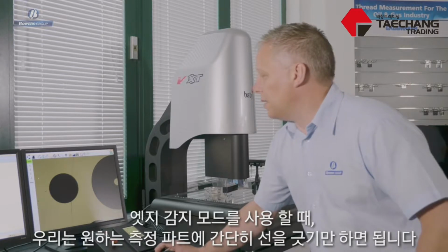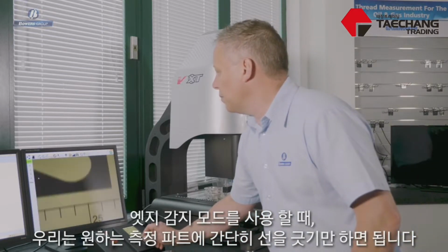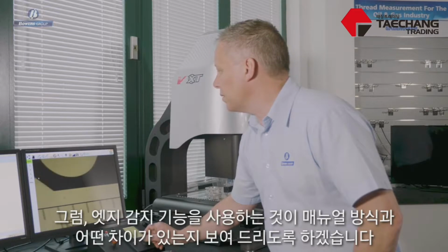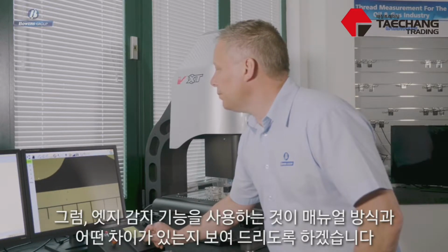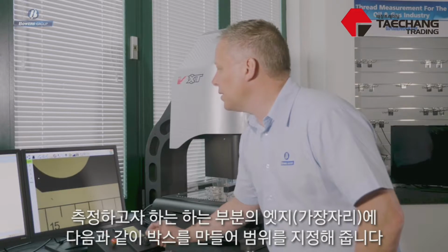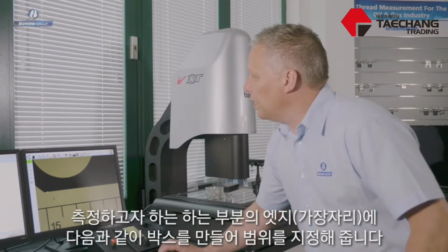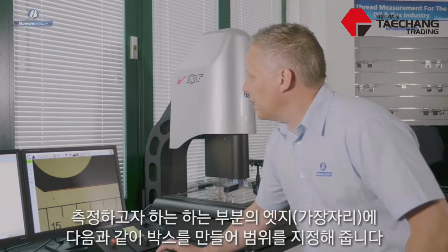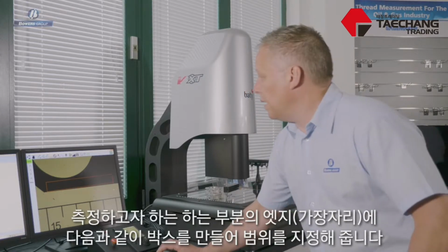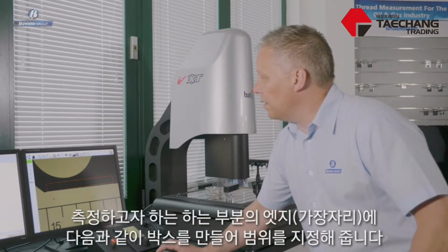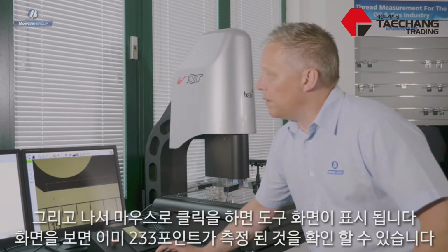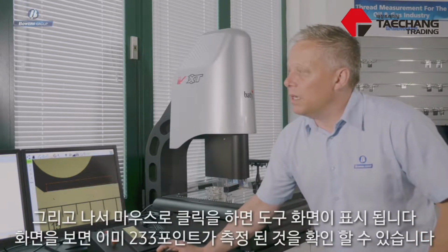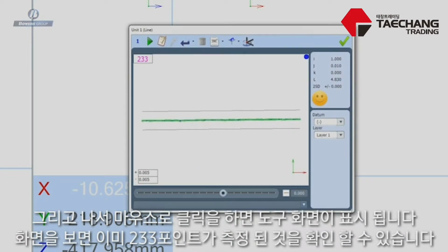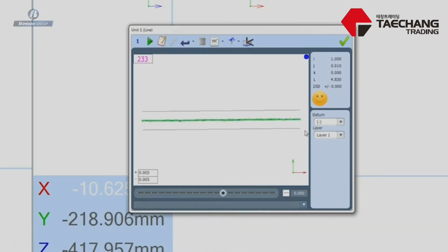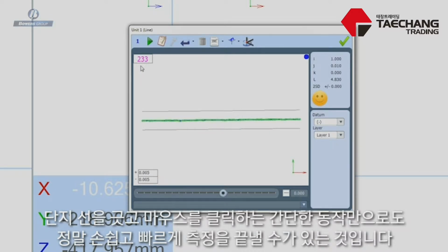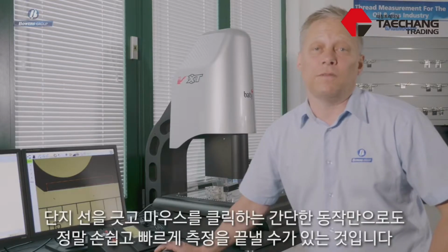So when we take edge detection measurements, I'm just going to line this part up so that we can start to show you the difference. With the video edge detection tools, I can simply draw a box over the edge of this line that I want to measure, and I'm creating a scanning width here, and with the next click of a mouse I've fired the tool, and you can see here that I've taken, in this case, 233 points in one mouse click. So the first thing that you can understand from that little exercise is vision's fast.